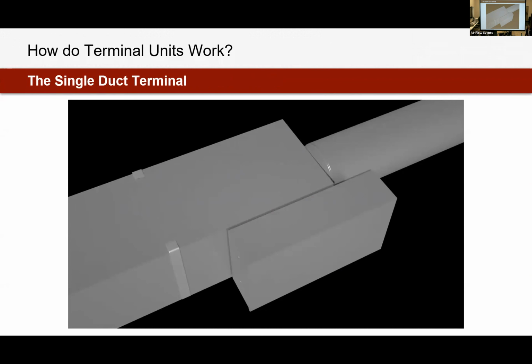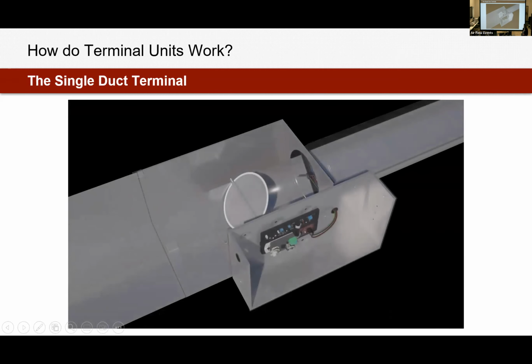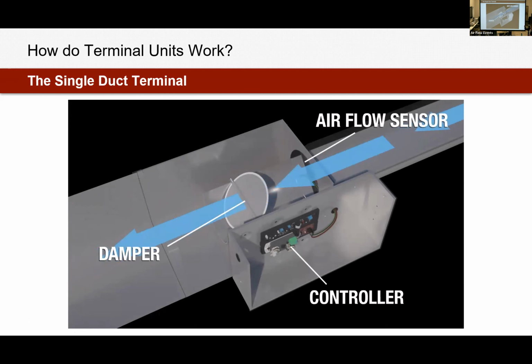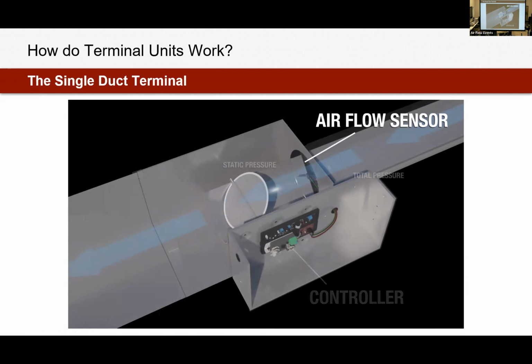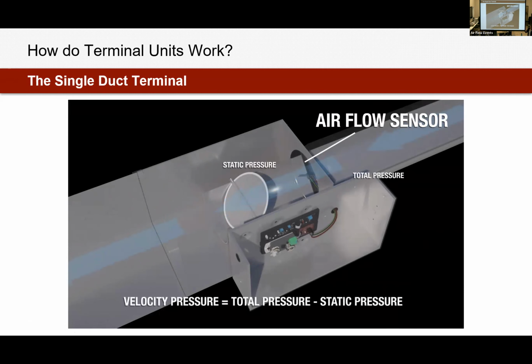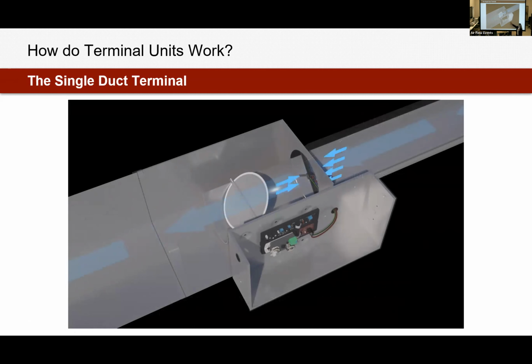The absolute most basic type of terminal unit is a single duct box. Your single duct is simply a rectangular box with a primary air valve. Inside of the box, you do have a damper. Through the box, we can see fresh air is flowing into the primary air valve across an airflow sensor. The damper is controlling that airflow, but it's being controlled by this controller.